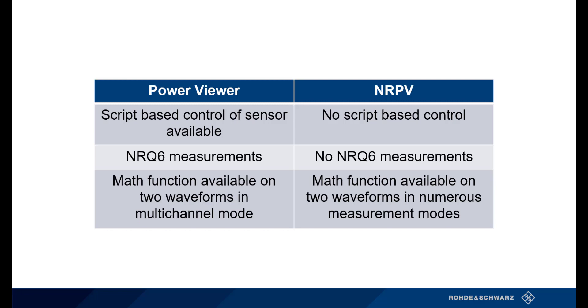Something else to notice is the programs' compatibility with the R&S NRQ6 sensor. NRQ6 is a frequency selective power sensor that has its own web GUI for measurements, but some basic measurements can be taken with Power Viewer. These measurements are not possible on NRPV. NRPV is capable of doing certain math functions on multiple waveforms you are measuring in numerous measurement modes, while Power Viewer has this capability only in multi-channel mode.